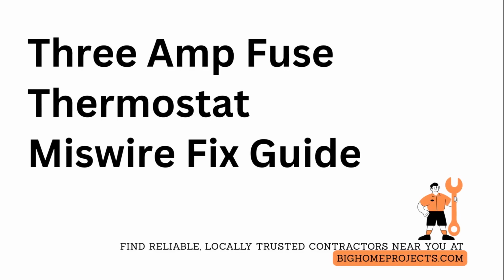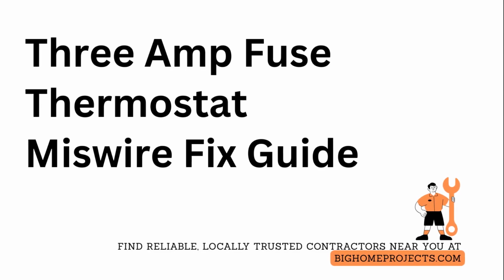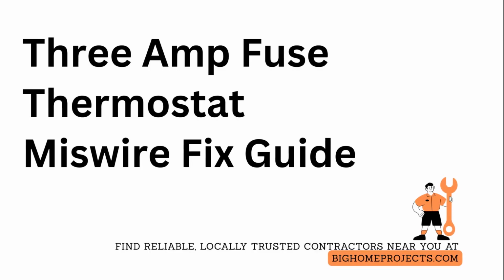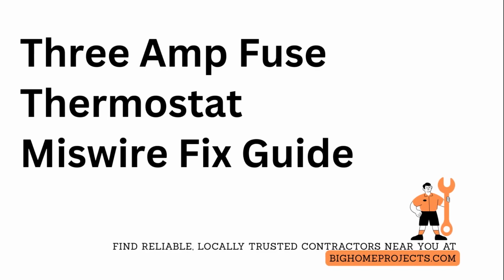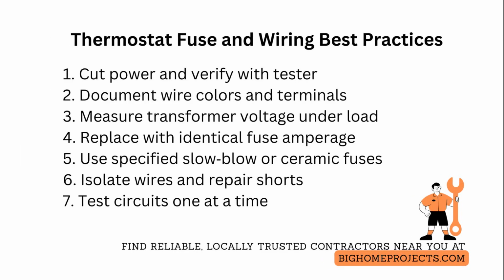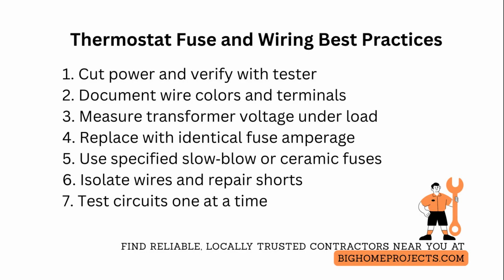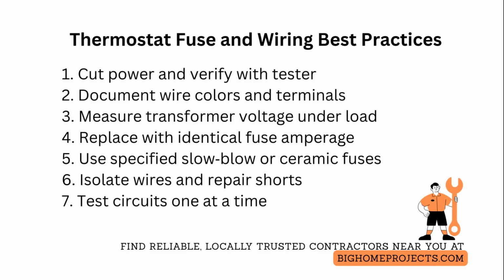Replace blown fuses with the exact labeled amperage to prevent further control board and transformer damage when fixing thermostat miswires. When replacing a thermostat after a miswire, first cut power at the breaker and verify with a non-contact tester. Then document every wire color and terminal label with a photo and written note. Do not assume wire colors match functions.